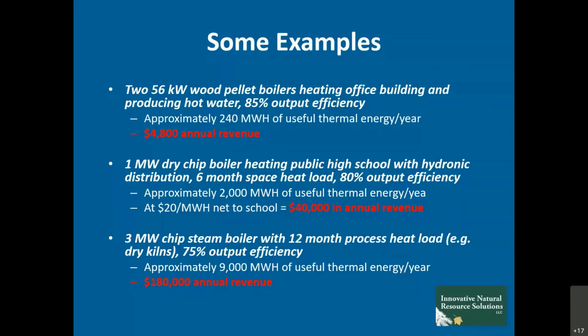A 1 megawatt dry chip boiler, or more likely multiple boilers ganged up, using dry chips to heat a public high school with a 6-month heat load and maybe domestic hot water, at 80% output efficiency, produces roughly 2,000 megawatt hours of useful thermal energy a year. At $20 net to the owner of the system, that generates about $40,000 a year in revenue. Jim's got some fantastic slides showing what a significant impact that has on your overall operating costs or your ability to pay down your initial capital investment at a much more accelerated rate.